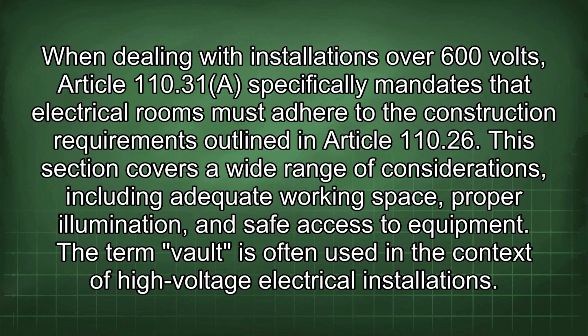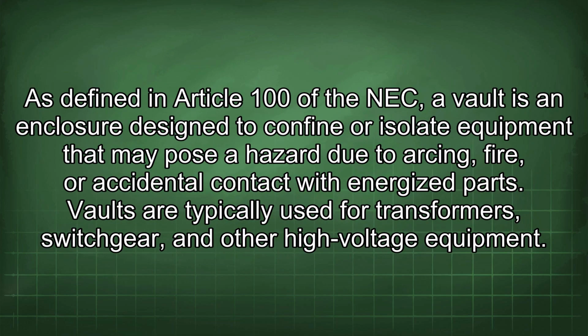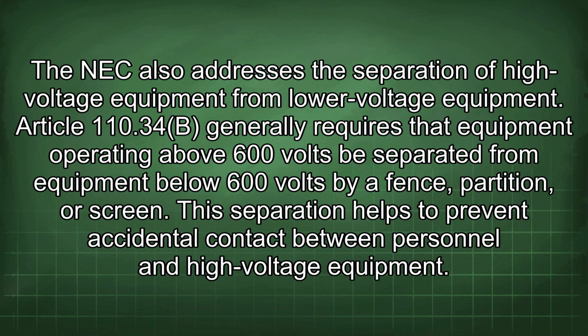The term vault is often used in the context of high-voltage electrical installations. As defined in Article 100 of the NEC, a vault is an enclosure designed to confine or isolate equipment that may pose a hazard due to arcing, fire, or accidental contact with energized parts. Vaults are typically used for transformers, switchgear, and other high-voltage equipment. The NEC also addresses the separation of high-voltage equipment from low-voltage equipment.